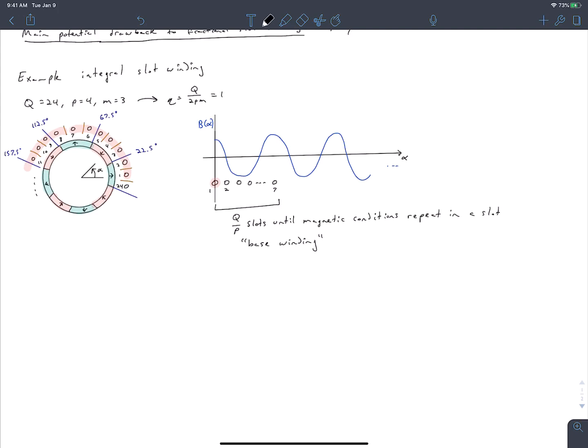For an integral slot winding, the base winding length is always Q over p slots. Because there are always q slots within each phase zone and q is an integer, our winding must repeat itself after one pole pair. This is different for a fractional slot winding, because q is no longer an integer — it's some fraction. Therefore the magnetic conditions in our slots will not necessarily repeat themselves after a single pole pair.